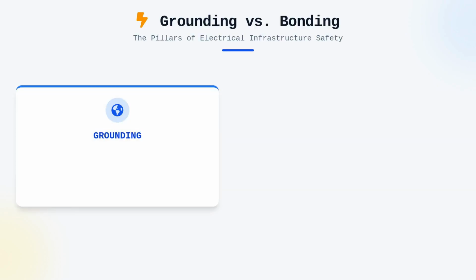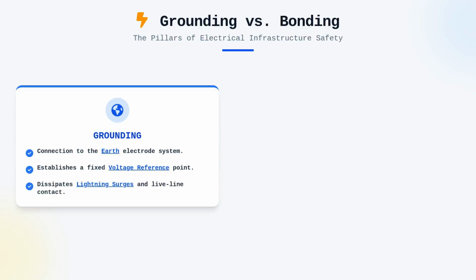In any complex building infrastructure, the distinction between grounding and bonding remains a point of persistent confusion, yet it is arguably the most vital concept in electrical safety. Grounding, in its strictest sense, refers to the intentional connection of a circuit or device to the earth, typically through a grounding electrode system. This earth connection serves as a reference point for voltage and provides a dedicated path for the dissipation of lightning surges or unintentional contact with live power lines.